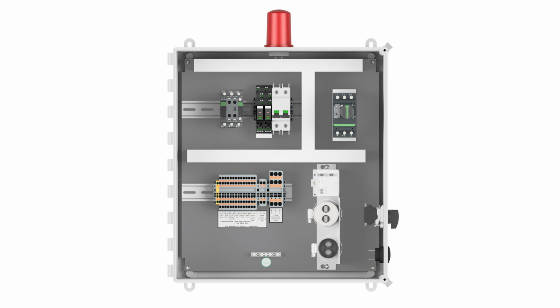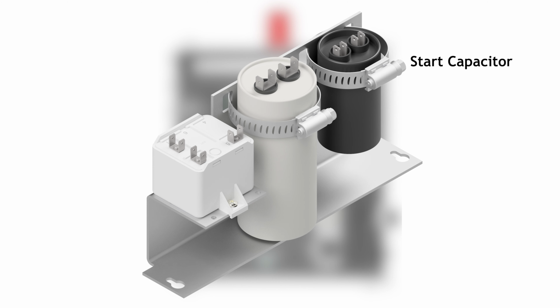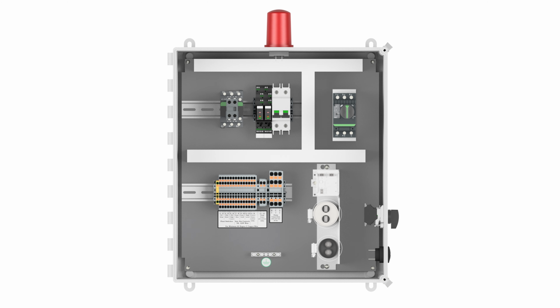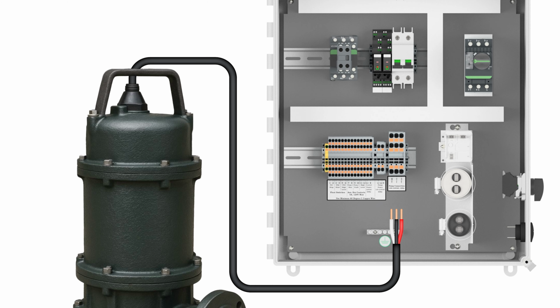A capacitor kit that is wired into a control panel will consist of 3 components: start capacitor, run capacitor, and a start relay. Each grinder pump manufacturer calls out the specifications of each component of the capacitor kit and is engineered specifically for the pump they are designed for. It is critical to understand that a 3-wire grinder pump installation with a control panel that has capacitor kits is our industry's most complex installation.